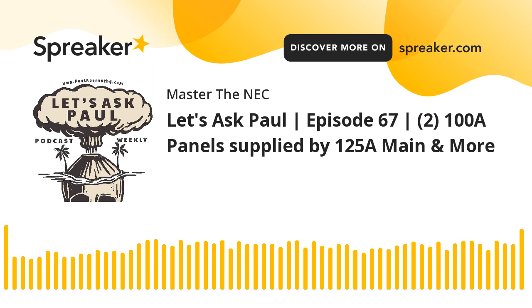You probably have gone through a continuing education class at some point, and they have added this information, and you're kind of bumbling on it. And you're thinking, well, do I have to have surge protective devices? Okay, so a couple things first. If you're just migrating to the 2020 edition of the NEC, then you probably remember that surge protective devices and surge arresters and all this type of stuff used to be in 280 and 285. Now it's been moved and it's in 242. So that gives you the information about the different types of SPDs and things like that.